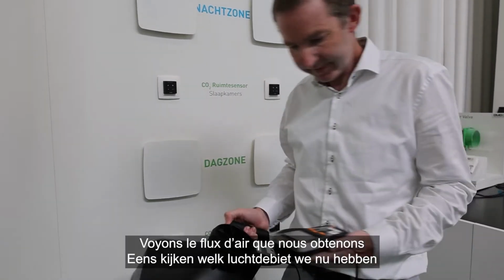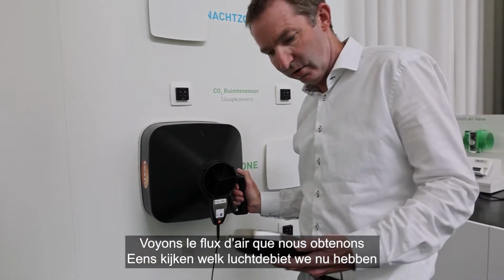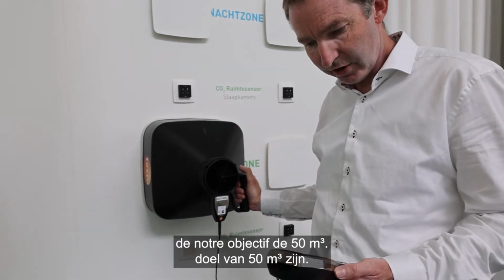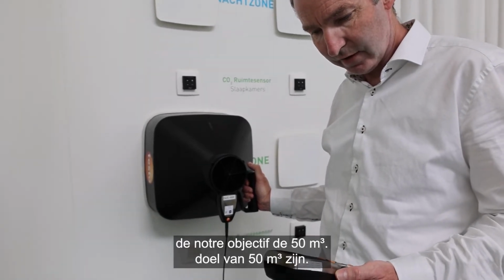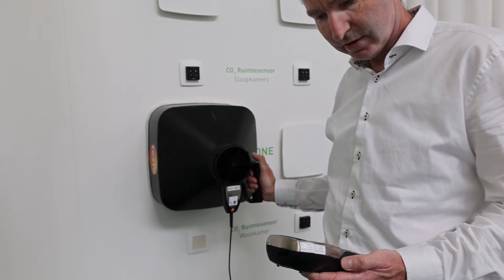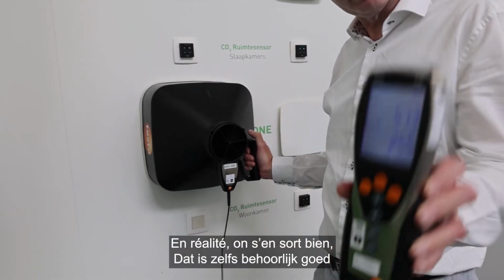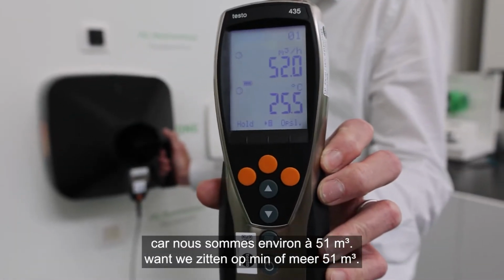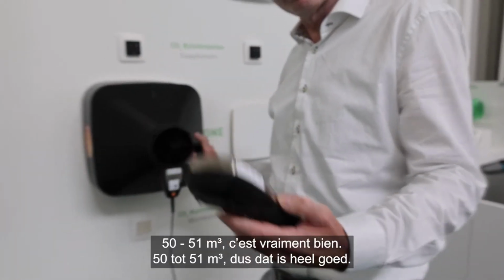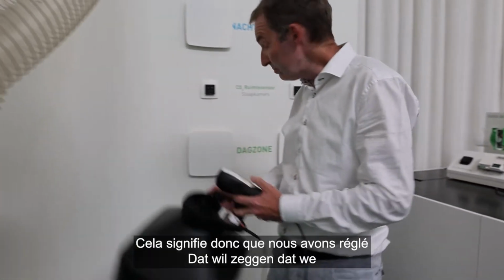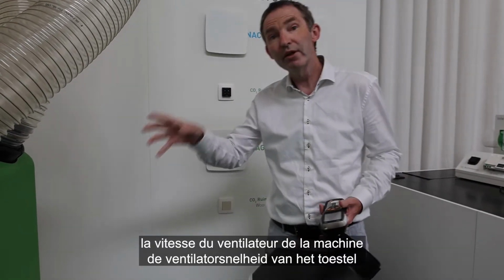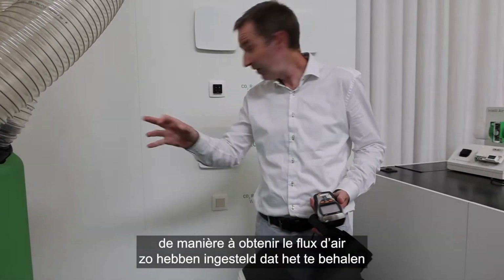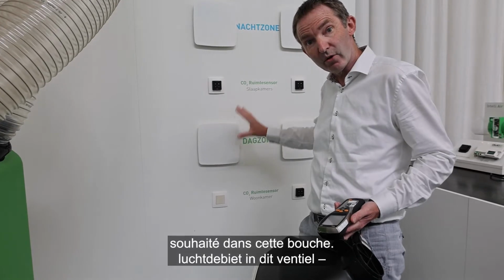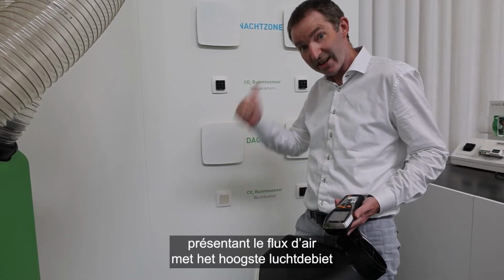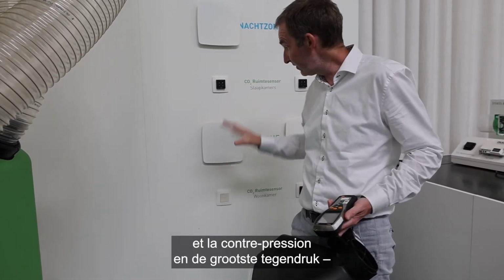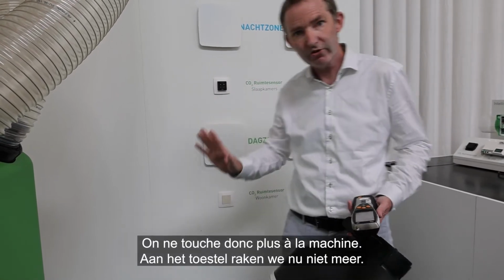Okay, so let's see how much airflow we have now and whether we are closer to our target of 50. Actually, I'm doing really well because look, we are at 51 or something. 50-51. So that is really good. So this means that actually we have set the fan speed of the machine such that the desired required airflow in this vent, remember it was the vent with the highest airflow and with the highest counter resistance, is met. Okay, so now we don't touch the machine anymore.